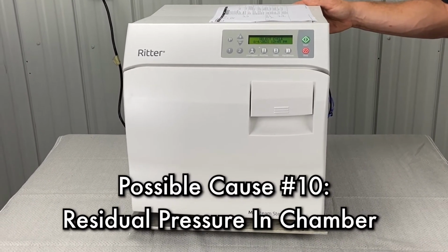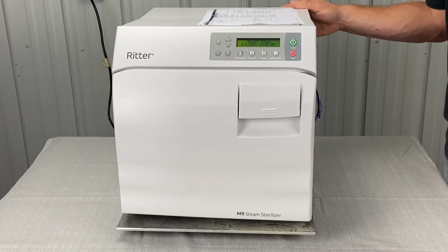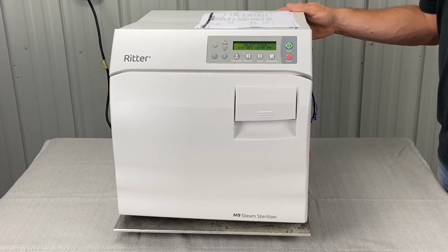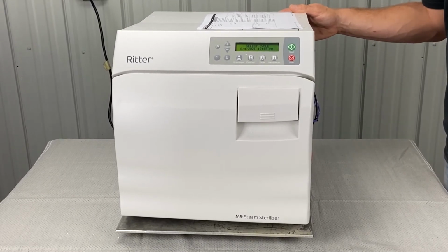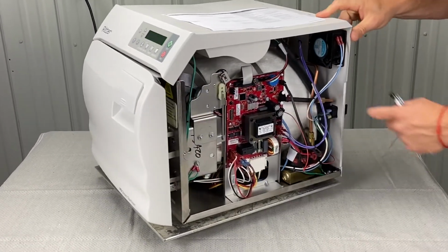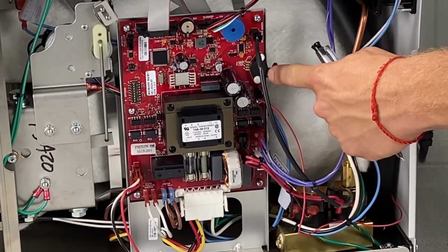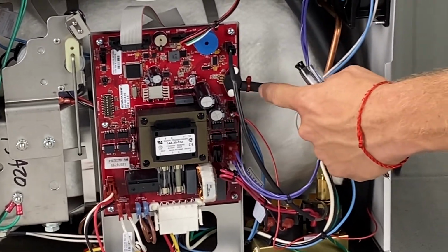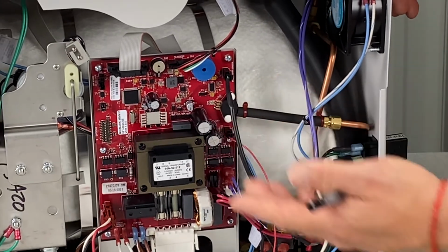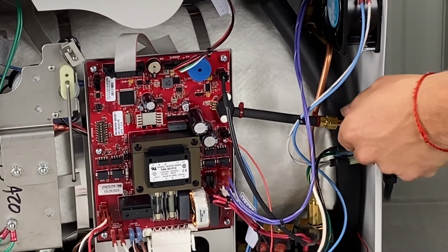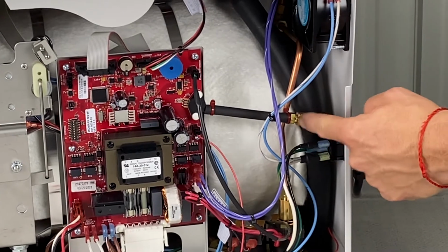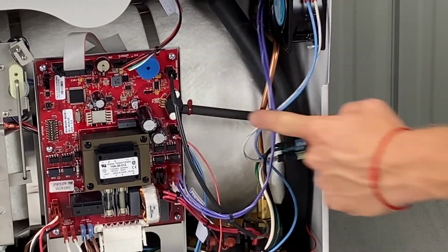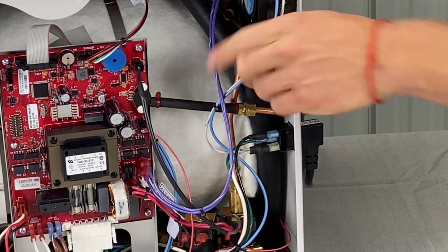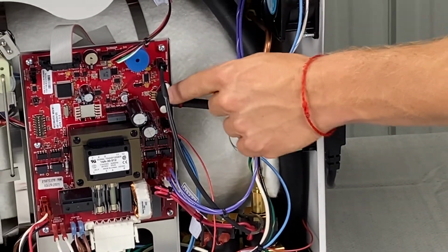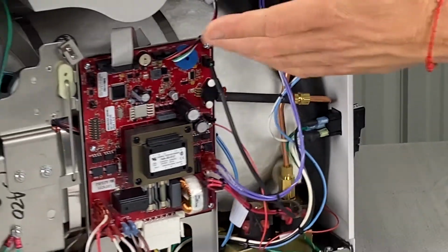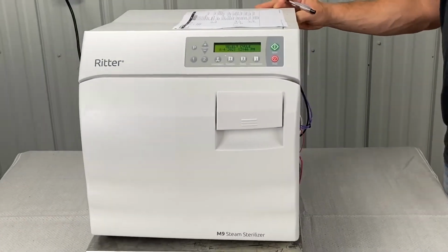Residual pressure in the chamber. Check for the chamber pressure when door motor is energized. Clear any restriction that could prevent chamber pressure from reaching the pressure transducer on the PC board. So this is the pressure transducer on the PC board. Somehow, some way, if something gets stuck in here, you may have some sort of issue. I don't see that too often, honestly, but also if this is not positioned in the right place, it should be at an angle like this. If it's pointing down, then water tends to flood this because it'll stay there even when the cycle's over. That could cause intermittent issues there.